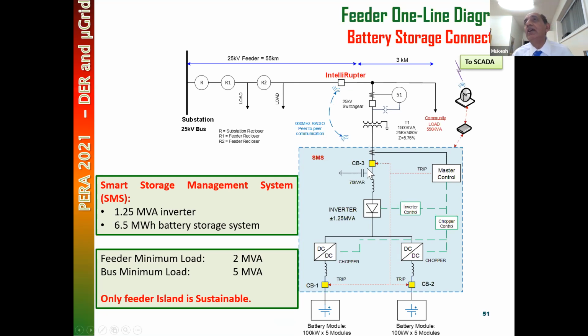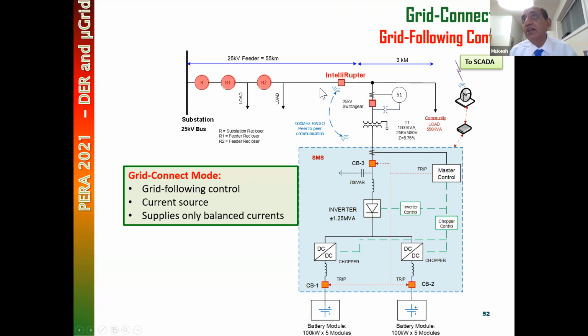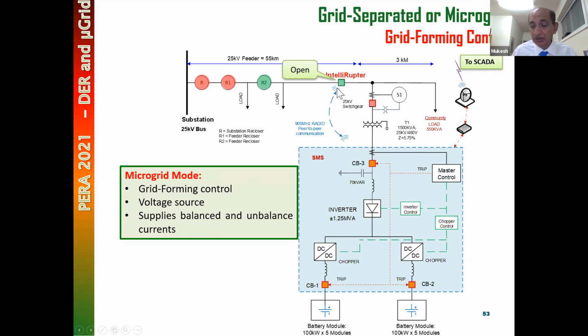So this IntelliRupter gives a signal to this inverter that it should go into microgrid mode. When it sees a forward fault, it does not give a signal. It says the fault is in front of me, the fault is here. Even if you form a microgrid, you're not going to help this community, so don't even form a microgrid. But if the fault is here, it's a reverse fault. But unfortunately, because of this battery source, this cannot see a reverse fault. I'm going to show you that later.